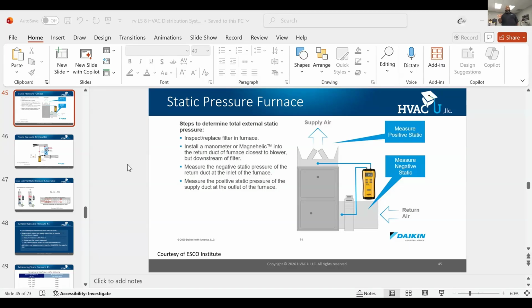So you would measure across the filter if you're trying to evaluate that. Maybe a part two we should think about in the future, after we get our air handler airflow measurement, is going back and making modifications, because you can actually take static pressure and look at certain parts of the system and see where the problem physically is. Now, when you look at MERV, a higher MERV rating is a more restrictive filter. Before you make that adjustment, Brett, you will have to verify that the duct system can handle that more restrictive filter.